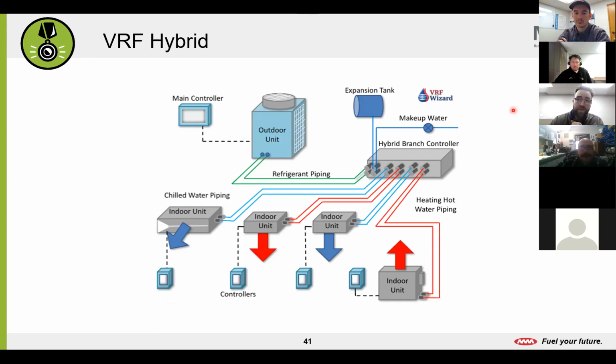And then we have VRF Hybrid. I've not actually seen one of these in the wild yet, but the principle of them is extremely cool. So what this allows us to be is as flexible as a VRF system is. A hybrid system allows us to be even more flexible. And the reason for that is if we look at the system here, we have our outdoor unit or our condenser unit. And then these green pipes here are our refrigerant lines. These are what's carrying our refrigerant, and it comes to our BCR branch controller, heat recovery unit, whatever manufacturer is calling it. And that's it as far as refrigerant.